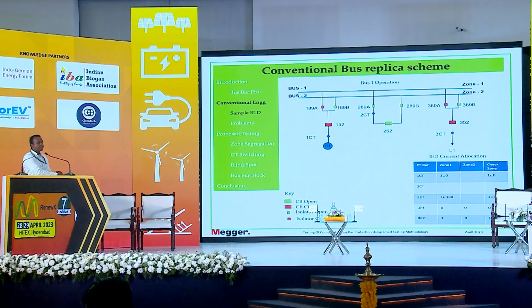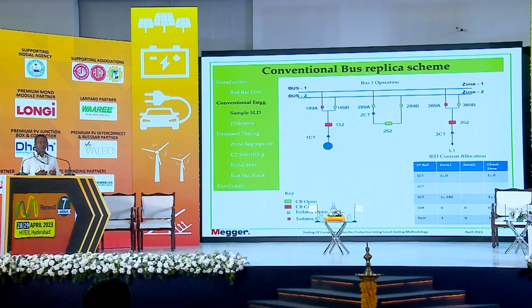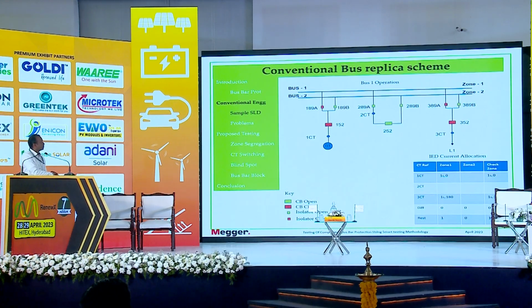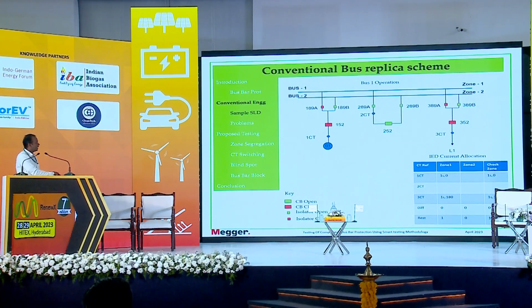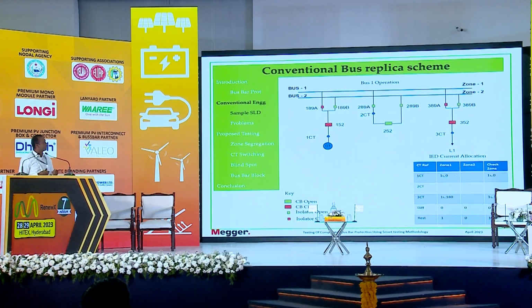And the angle is actually based on how the current is flowing. So current flowing towards the bus, we take it as 0, and the current flowing away from the bus, we take it as 180 degree. So when we vectorially add this, 1 angle 0 plus 1 angle 180 would be 0. So that's the differential current, and restraining current follows the principle of maximum current, whichever current is high. So we can see differential current is 0, the system is healthy.